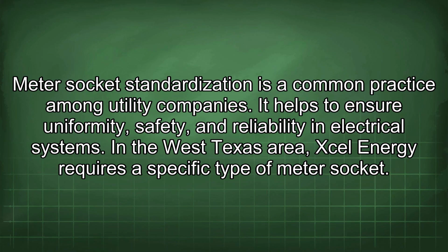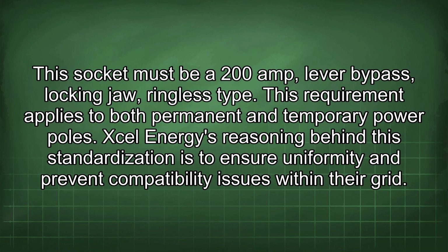Meter socket standardization is a common practice among utility companies. It helps to ensure uniformity, safety, and reliability in electrical systems. In the West Texas area, Xcel Energy requires a specific type of meter socket. This socket must be a 200 amp lever bypass, locking jaw, ringless type. This requirement applies to both permanent and temporary power poles.